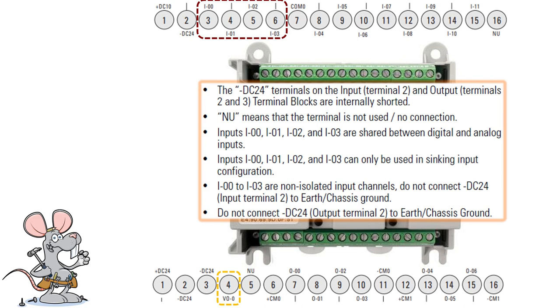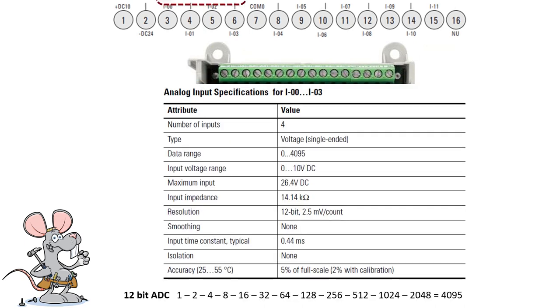Inside the box, the electronics support those four terminals — 0, 1, 2, and 3 — as straight digital on/off, or they have an ADC circuit. So you can configure those first four for analog inputs. Inputs 0, 1, 2, and 3 can only be used in sinking input configuration. These four inputs have a data range of 0 to 4095, meaning it's 12-bit A-to-D conversion. 12-bit is not high resolution — your analog input will come in 4,096 steps between 0 and 10 volts.